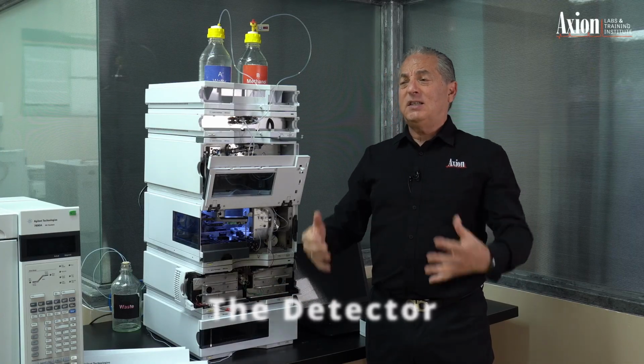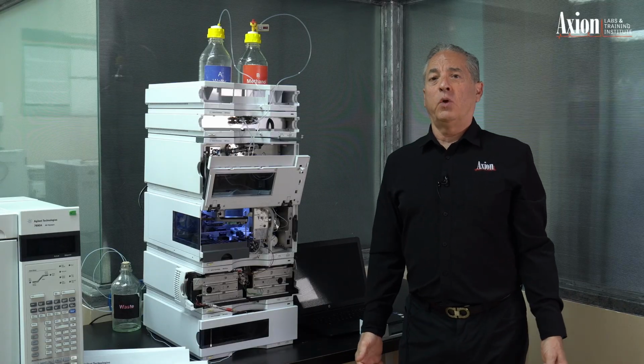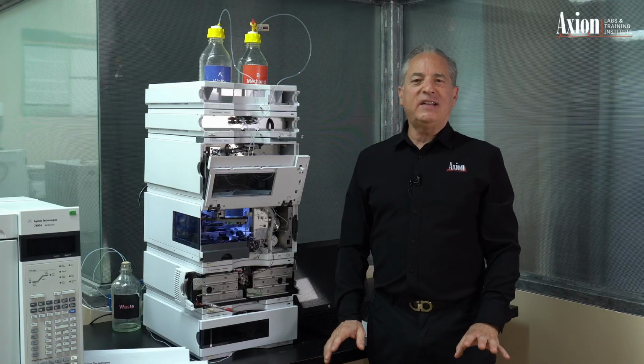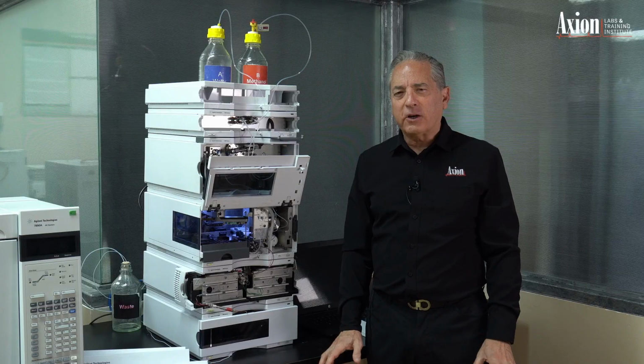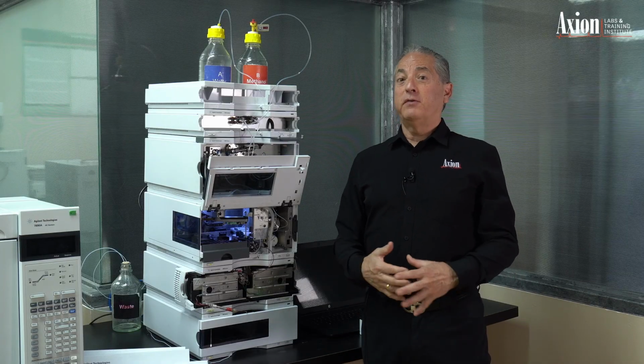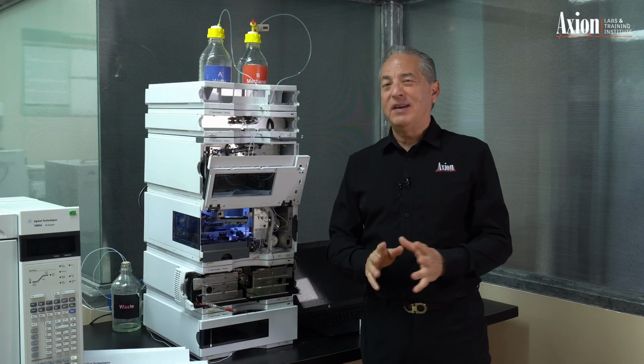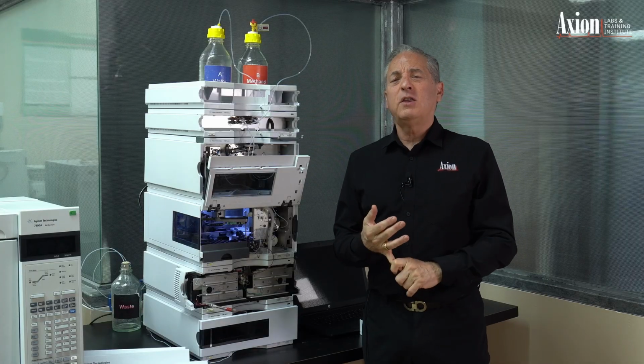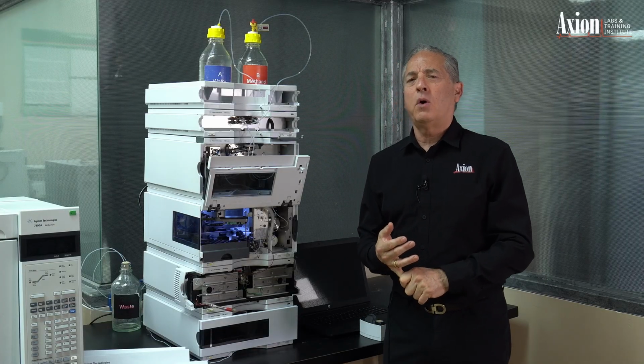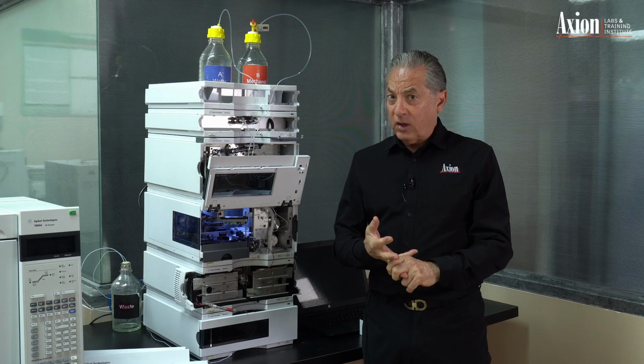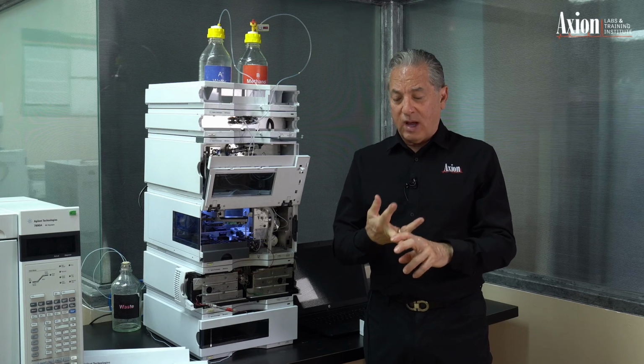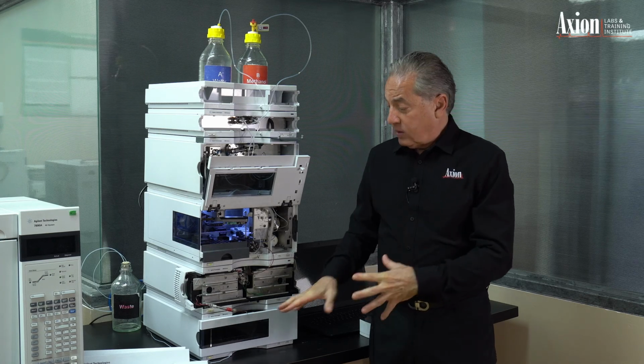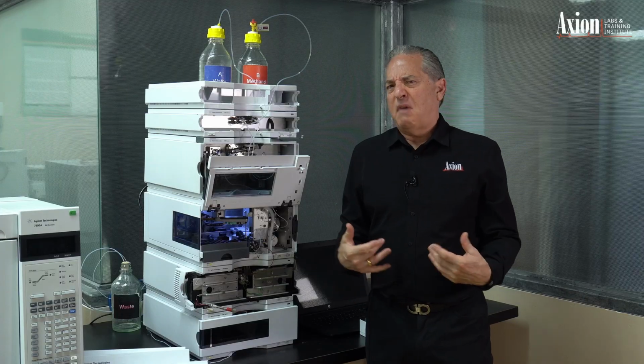Well, just as in GC, we have a lot of different detectors in the LC world, but we have one that dominates, and that's the UV-Vis. So UV-Vis detector, there's different flavors of it, is what I like to call it. There's different types of it. There's the fixed wavelength UV-Vis. Those are not very common anymore. There's the variable wavelength, which are really common. There's a multiple wavelength, sort of common. And there's the diode array, which is what this is, which is also very common, my favorite design.